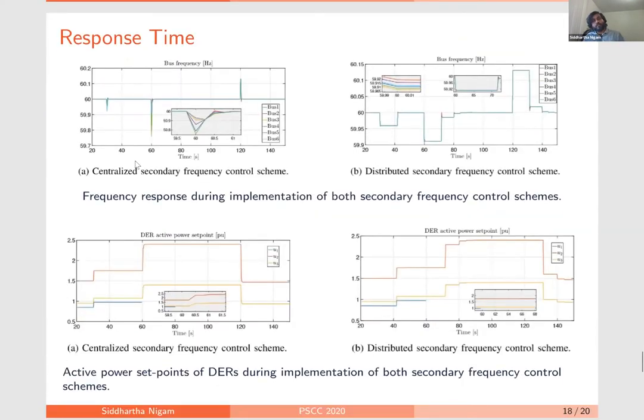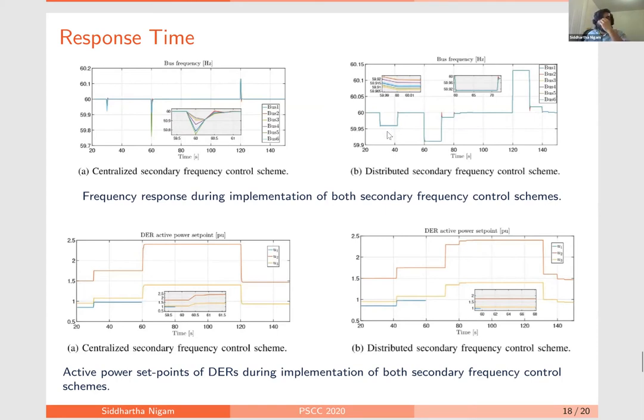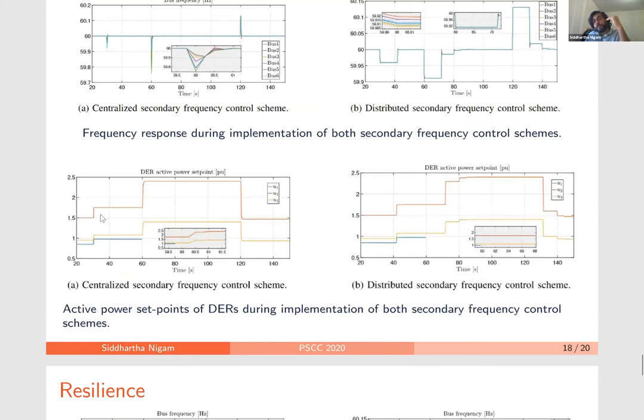In terms of response time, the centralized control node pulls information from DER and load buses quickly, computes the average frequency error, passes it to PI control, and essentially instantaneously takes the frequency error back to zero — or equivalently brings the frequency back to 60 Hz — at each perturbation event at 30 seconds and 60 seconds. In the distributed scheme, it still accomplishes the job, but it takes significantly more time — in this case about 11 seconds. These are the inverter setpoint updates for the three inverters in the six-bus islanded AC microgrid.